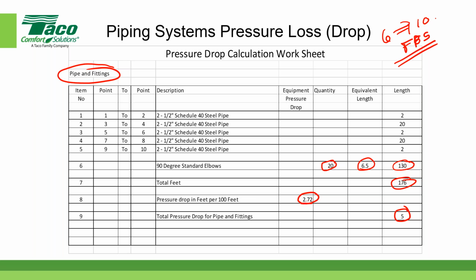If you get much higher than 10 feet per second, you run the risk of wearing the pipe out prematurely. When the water flows through the pipe and hits an elbow, it slams into that elbow, and over time it'll cause that elbow to erode and eventually fail or leak. If it's much lower than 6 feet per second, then the air bubbles entrained in the pipe will attach themselves to the inside wall of the pipe, and they'll stay there and help corrode the pipe. So you want high enough velocity to move the air along, but not so high that you slam into fittings and wear the pipe out prematurely, which is why most engineers will have a range.